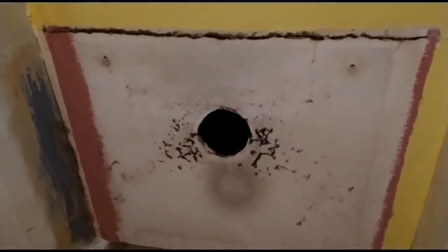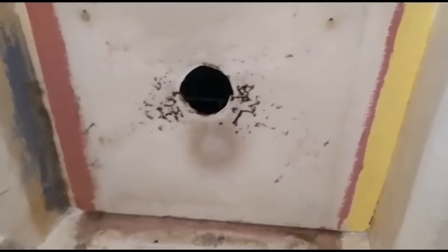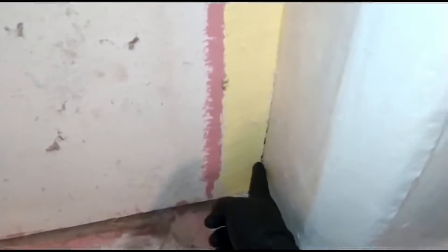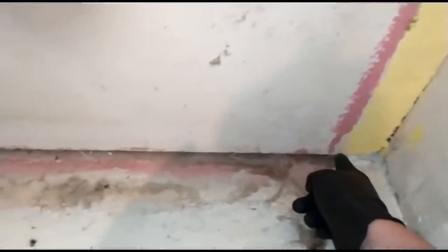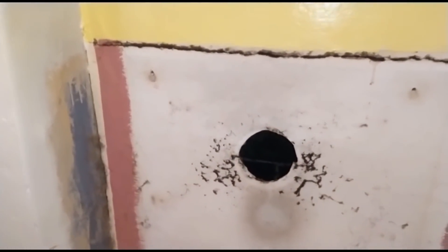Pulling it forward — and it's out, and all we have is a hole. The hole for the flue outlet from the fire. It's meant to have a closure plate — for the apprentices out there, it should have a nice closure plate fitted. Also, when things aren't sealed around the edges, that gives you a little warning.